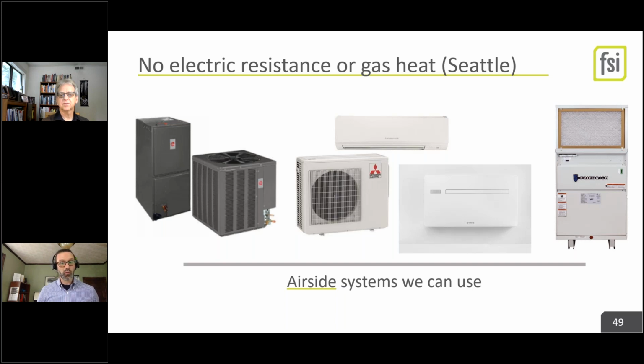The only thing you've got to watch out for on those VPACs or PTACs is your electric capacity that cuts over at 45 degrees. You'll note on that exceptions, there are limits on how much electric capacity you can have, and that could be a limiting factor depending on your exact project situation and how much heat you need at low temperatures.